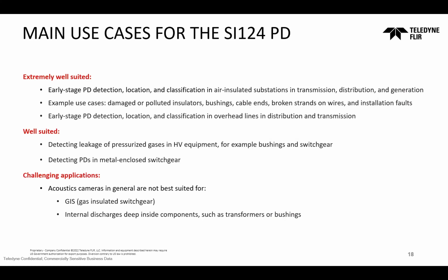For leakage of pressurized gases, if it has gas detection or air and gas detection, we need to be careful with this statement. The leak size has to be relevant. For example, with SF6, the leak size has to be very significant for the camera to find it, and those SF6 leaks at that level, maybe over 15 kilos per year, are rare. They're too big. So yes, you can find them, but I'd be careful here. I wouldn't use this as a selling point for the camera.